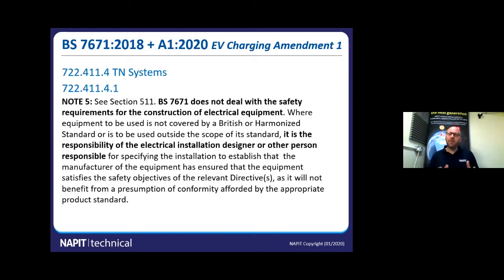There is a note with this, note 5, and it basically goes along the lines that the regs don't deal with the construction of electrical equipment. So it's your responsibility to make sure that you've got the right equipment for the job, and you need to check with the manufacturer and ask, is your equipment safe for installation on PME? If they've got some sort of declaration of conformity or statement that says their equipment meets condition 1, 2, 3, 4, or 5, great. We would recommend that you keep that declaration of conformity with your design paperwork, or even with the certificate, so that you can prove at a later date, if there is any sort of further backlash, that you've installed the equipment, adhered to this note, and checked that the equipment does meet the correct standards.